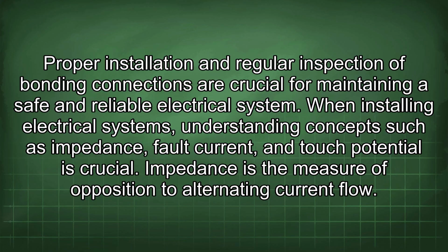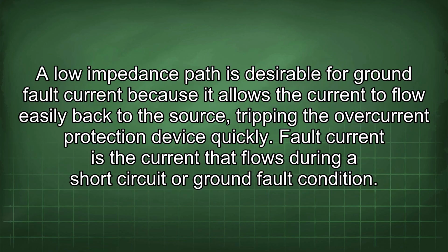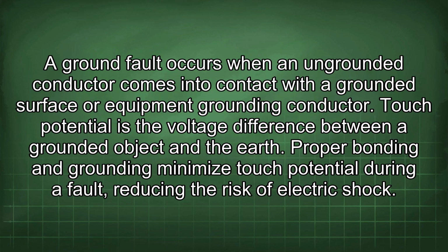electrical system. When installing electrical systems, understanding concepts such as impedance, fault current, and touch potential is crucial. Impedance is the measure of opposition to alternating current flow. A low impedance path is desirable for ground fault current because it allows the current to flow easily back to the source, tripping the overcurrent protection device quickly. Fault current is the current that flows during a short circuit or ground fault condition. A ground fault occurs when an ungrounded conductor comes into contact with a grounded surface or equipment grounding conductor. Touch potential is the voltage difference between a grounded object and the earth. Proper bonding and grounding minimize touch potential during a fault, reducing the risk of electric shock.